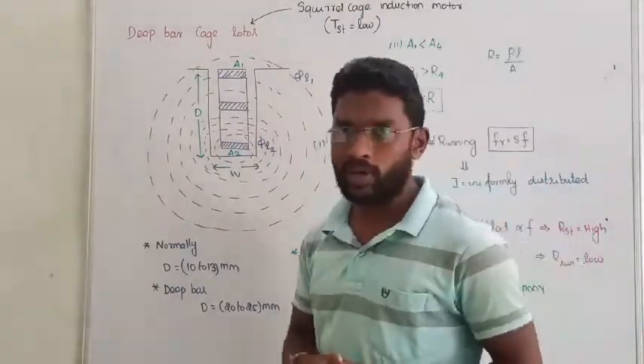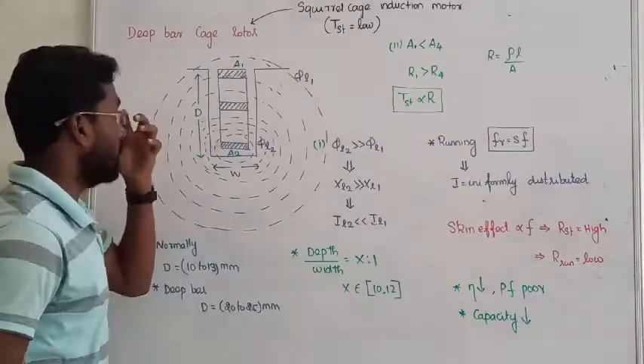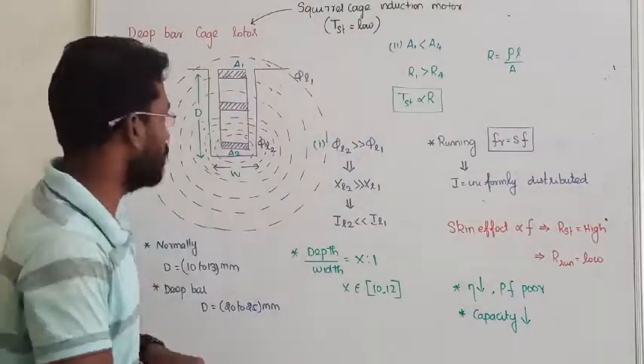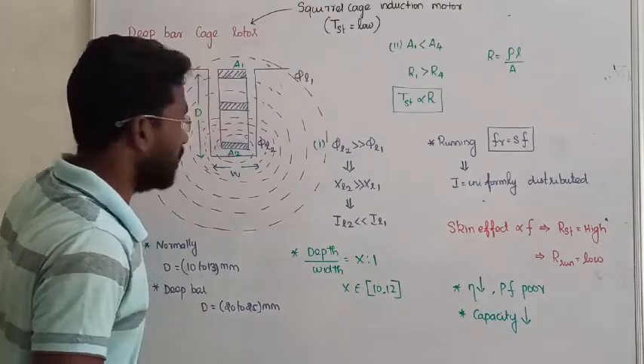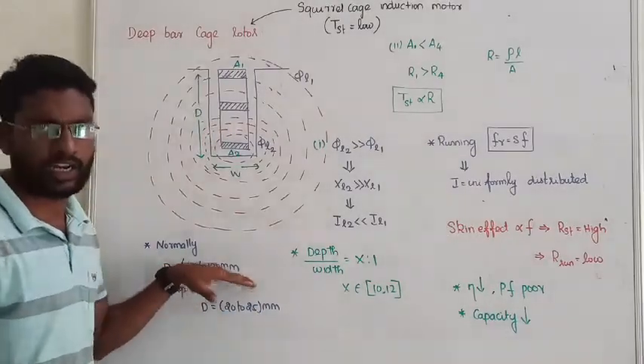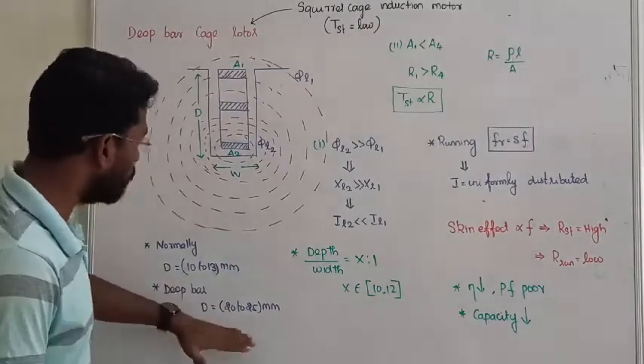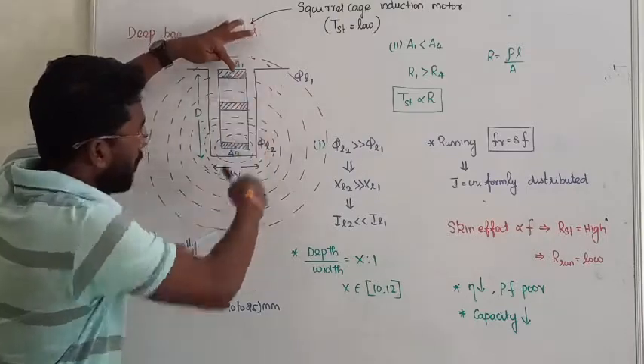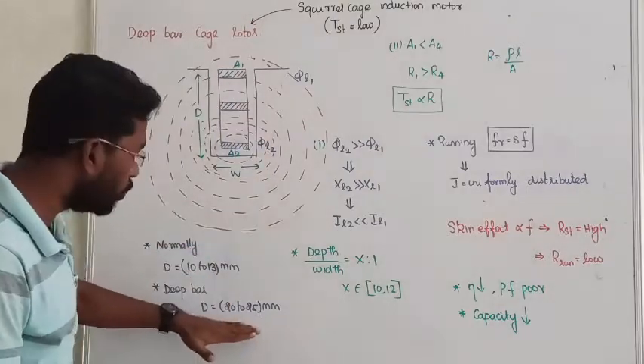What we are doing is, in rotor, we locate the bars or the slots or the conductors. We increase the depth of the bar. Usually, in normal cases, we have certain dimensions. We increase this from 10 to 25 millimeters.